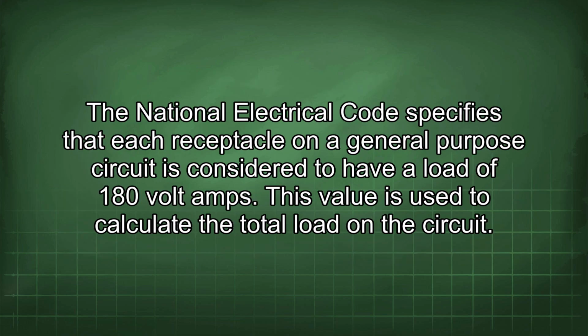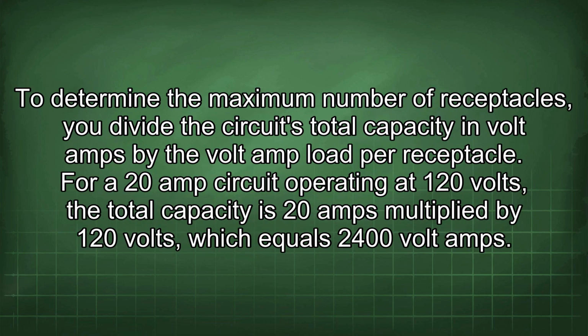The National Electrical Code specifies that each receptacle on a general-purpose circuit is considered to have a load of 180 volt amp. This value is used to calculate the total load in the circuit. To determine the maximum number of receptacles, you divide the circuit's total capacity in volt amps by the volt amp load per receptacle. For a 20 amp circuit operating at 120 volts, the total capacity is 20 amps multiplied by 120 volts, which equals 2400 volt amps.